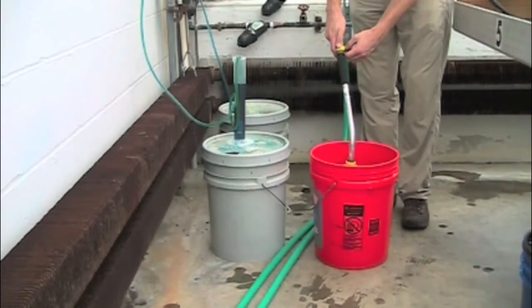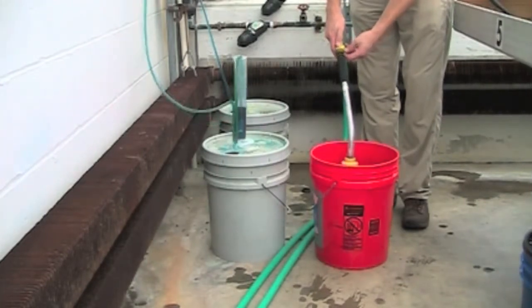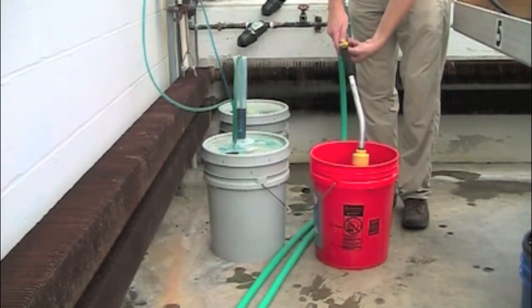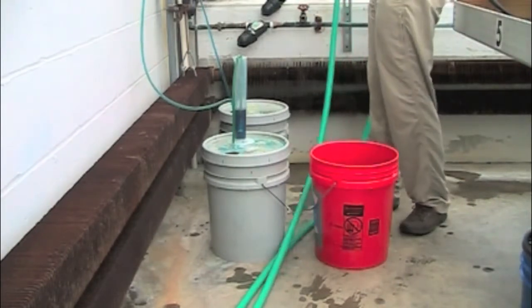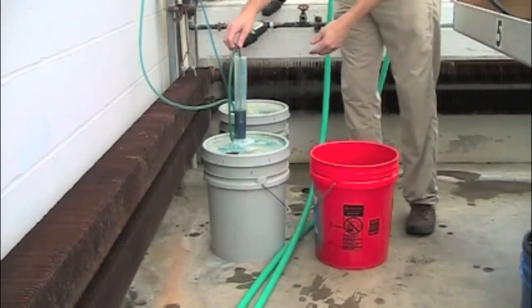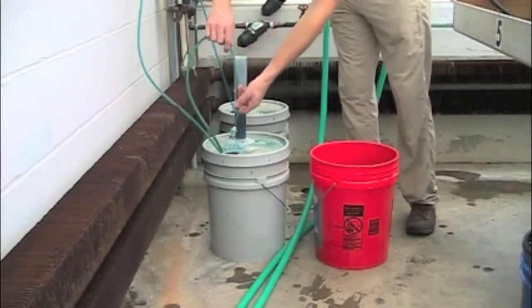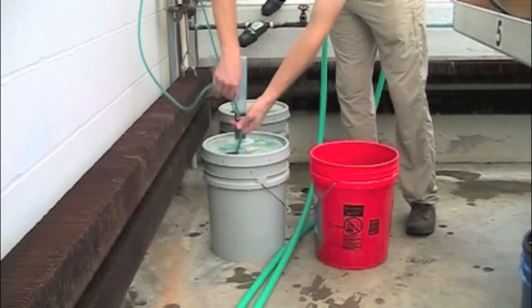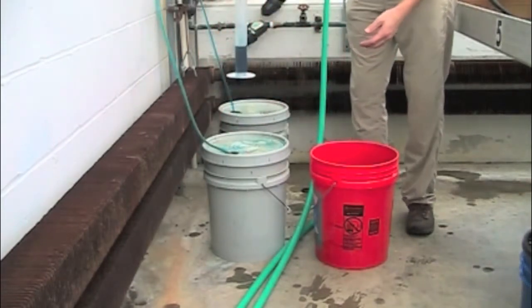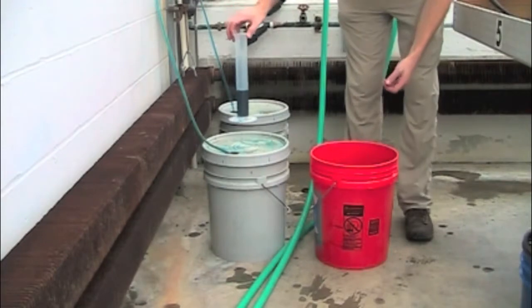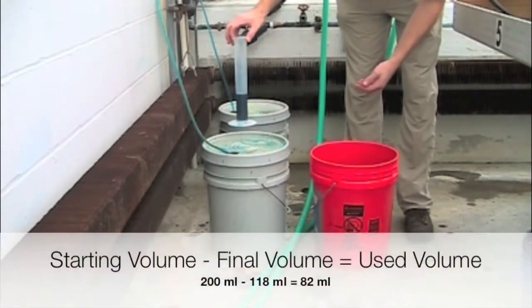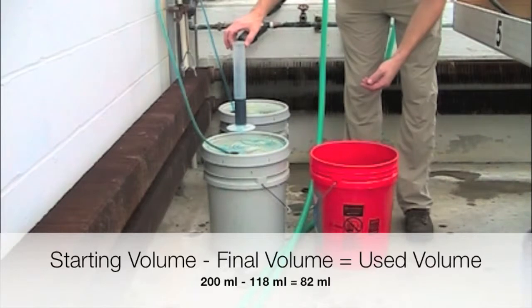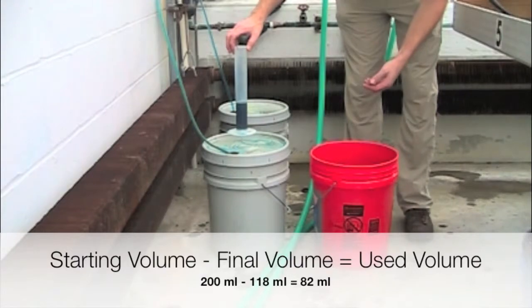The larger volume of water that you use will give you more accurate results, but in most cases, using between 4 and 5 gallons of water works well. Once the bucket is filled to 16 liters, the water is turned off and the lead from the injector is removed from the graduated cylinder. We now look at how much concentrate is left in the graduated cylinder. There are 118 milliliters left, which means to fill our bucket to 16 liters, we used 82 milliliters of concentrate.